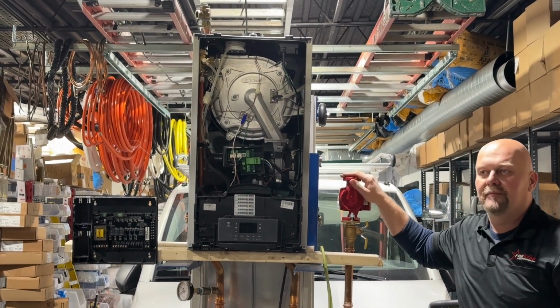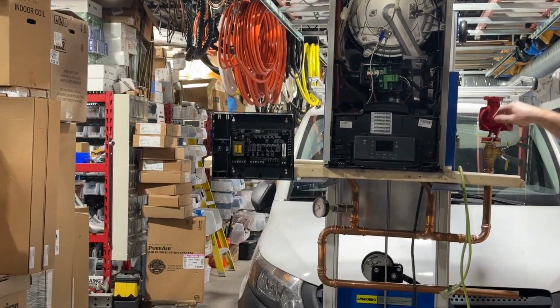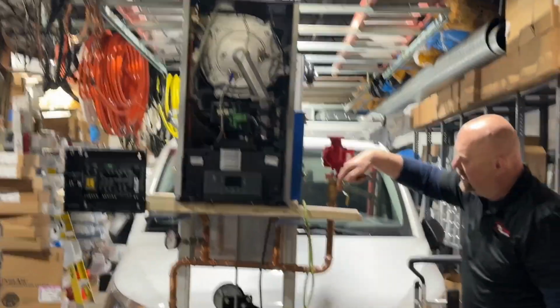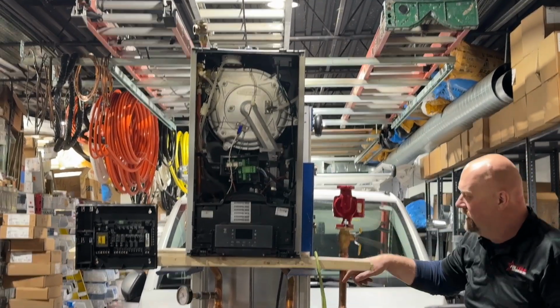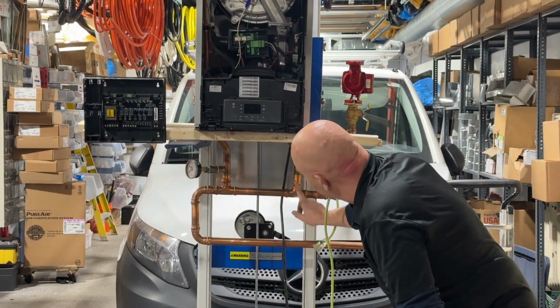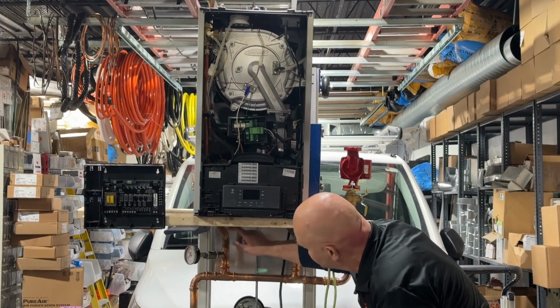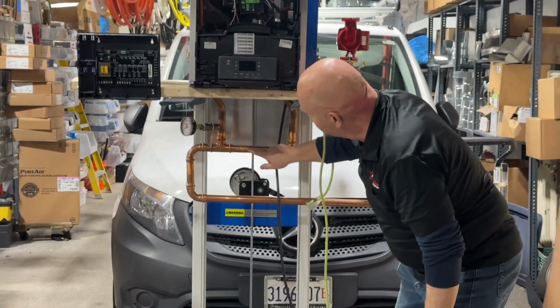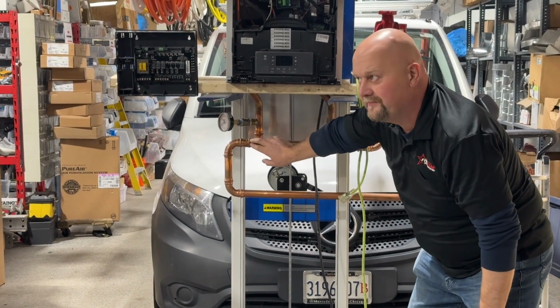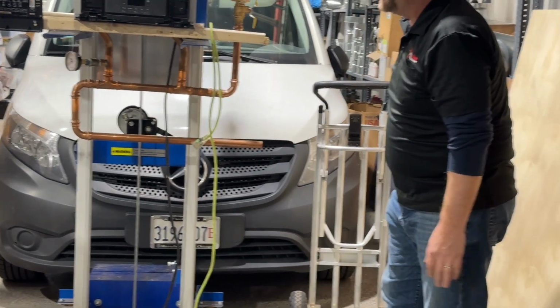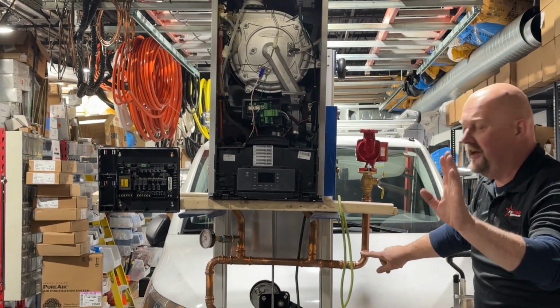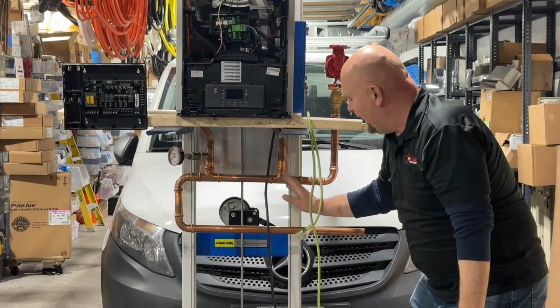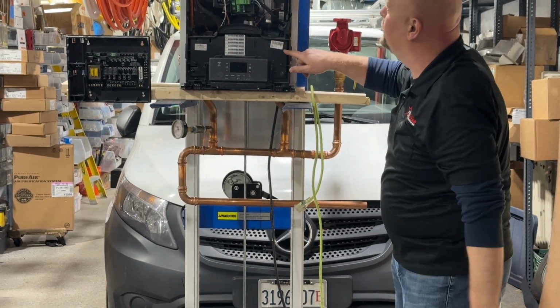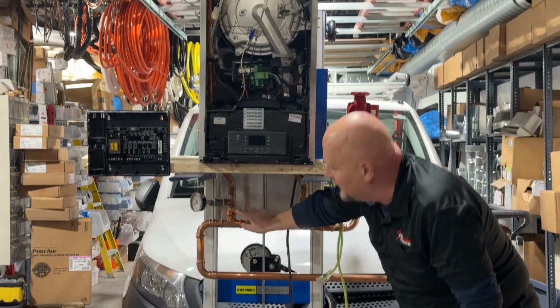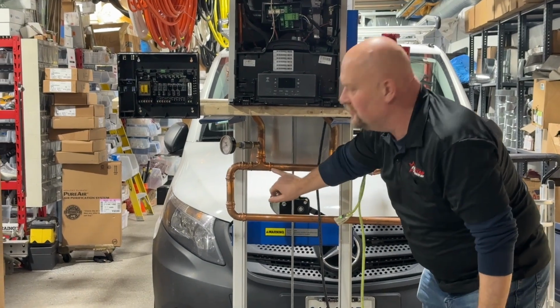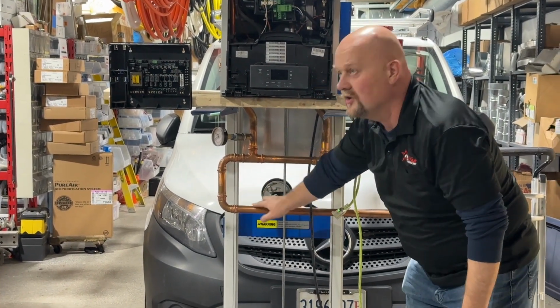For that, you're going to need a second pump out here. Now, if you notice, this pump arrows towards the boiler. So, if you see the water flow, this is from the radiators, comes down through here. Some of that water will go up to the heat exchanger and come back down on the supply side from the boiler. Some of it will go straight through. They will then mix right there and continue moving on to the radiators. So what you're going to have is, let's say, 100-degree water coming here. Half of it will go up to get heated up because this pump will draw it up to the top. It'll come back really hot here, like at 180 degrees, mix with 100-degree water, and it'll come out as 140.